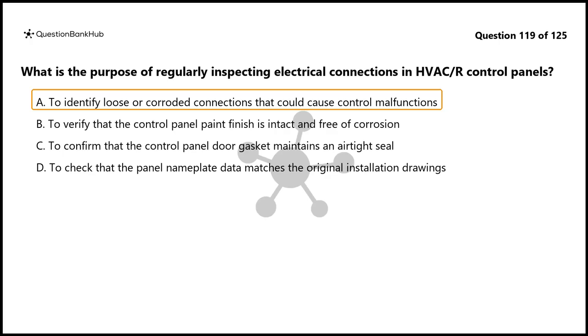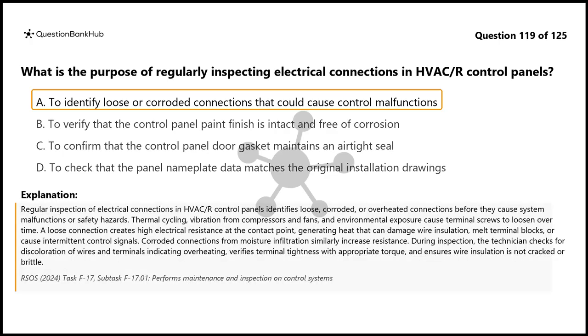The correct answer is A. Regular inspection of electrical connections in HVAC/R control panels identifies loose, corroded, or overheated connections before they cause system malfunctions or safety hazards. Thermal cycling, vibration from compressors and fans, and environmental exposure cause terminal screws to loosen over time.